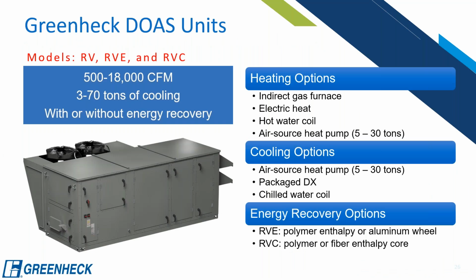So let's talk about what Greenheck has in terms of DOAS options. We have the models RV, RVE, and RVC. That's from 500 CFM up to 18,000 CFM, and we can do 3 to 70 tons of cooling with DX. Now, with heating options, it's not as relevant anymore, but we can do indirect gas heat, we can do electric heat, we can do hot water coils, we can even do steam coils. It's not listed there, but we can do steam coils. And most importantly, one thing to point out here is that we have an air source heat pump up to 30 tons. We can also do packaged DX and chilled water.